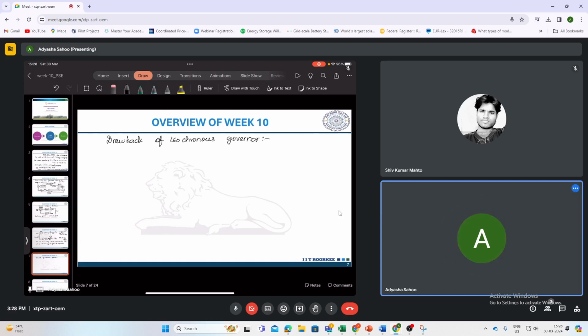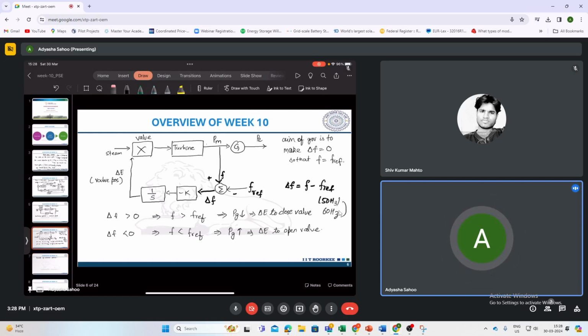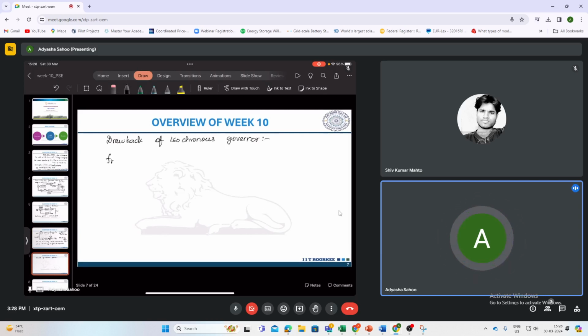But if we have two or more generators in parallel in an area supplying the load, what will happen is basically this F reference that we set. F reference for each generator, in case of two or more generators supplying the load, cannot be exactly the same, because that setting that we do, we cannot keep it exactly the same for all the generators. There will be a certain mismatch in this reference frequency for each generator.